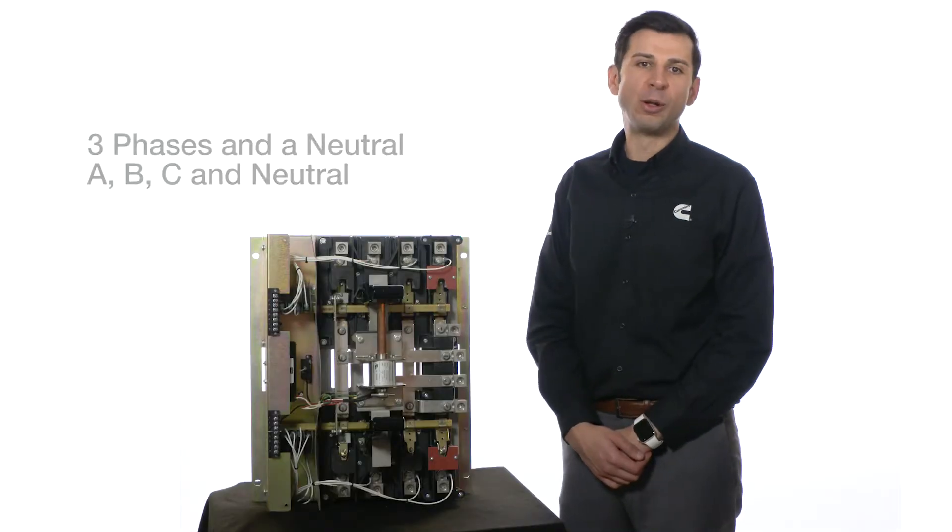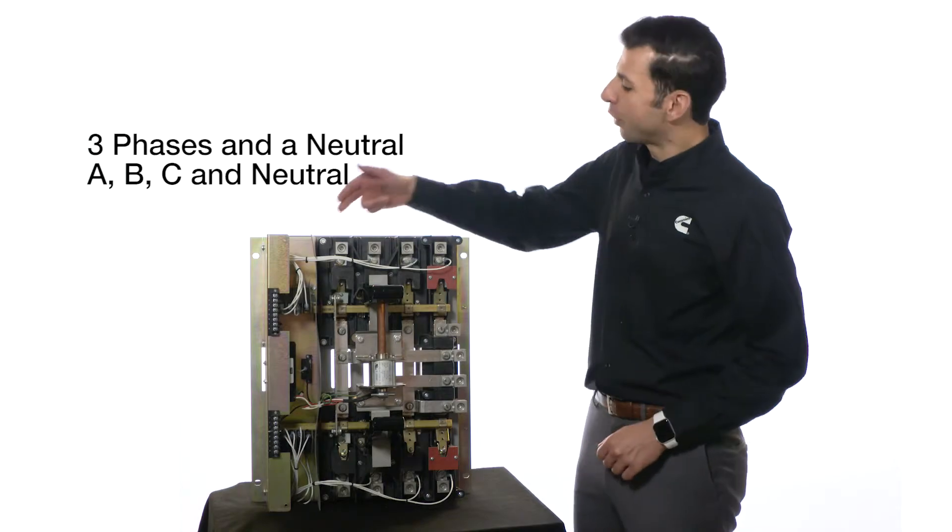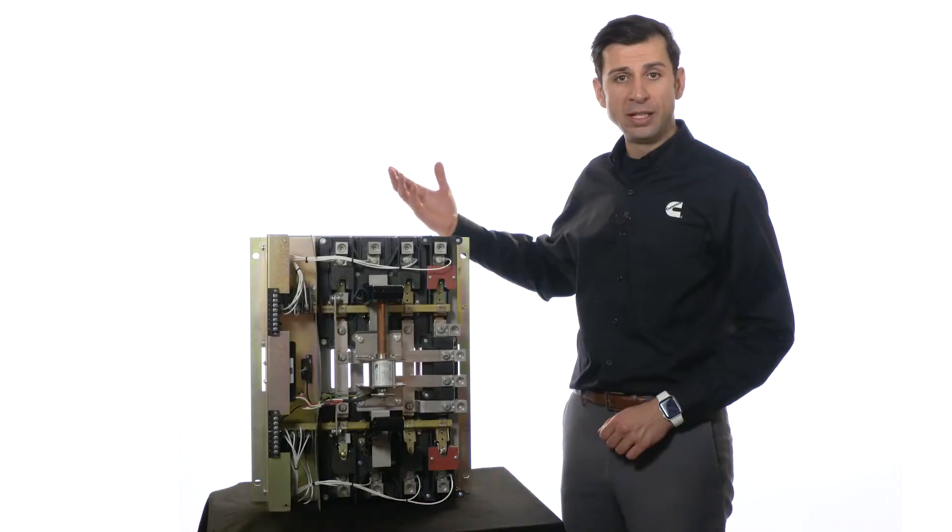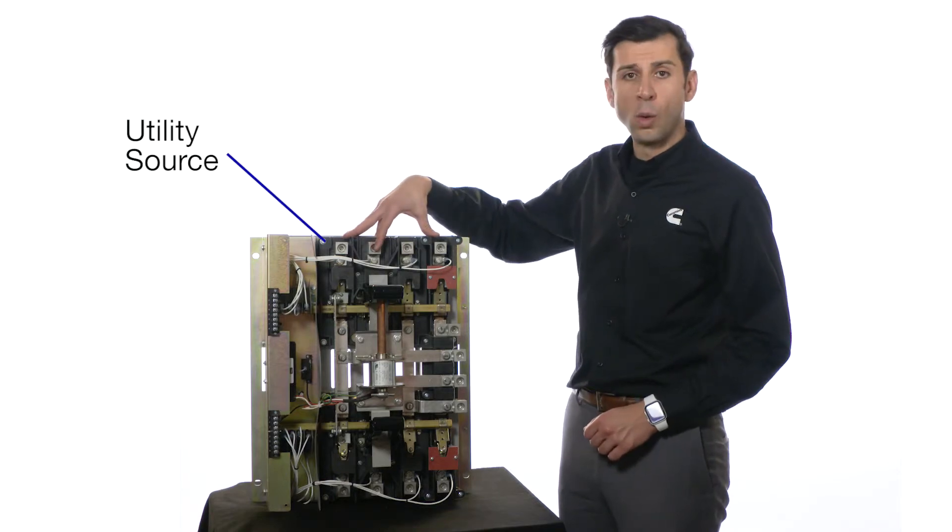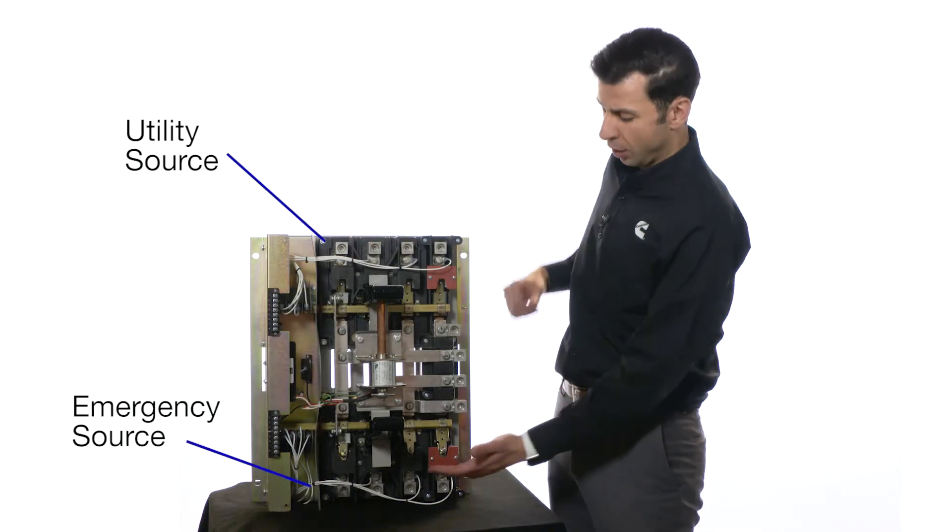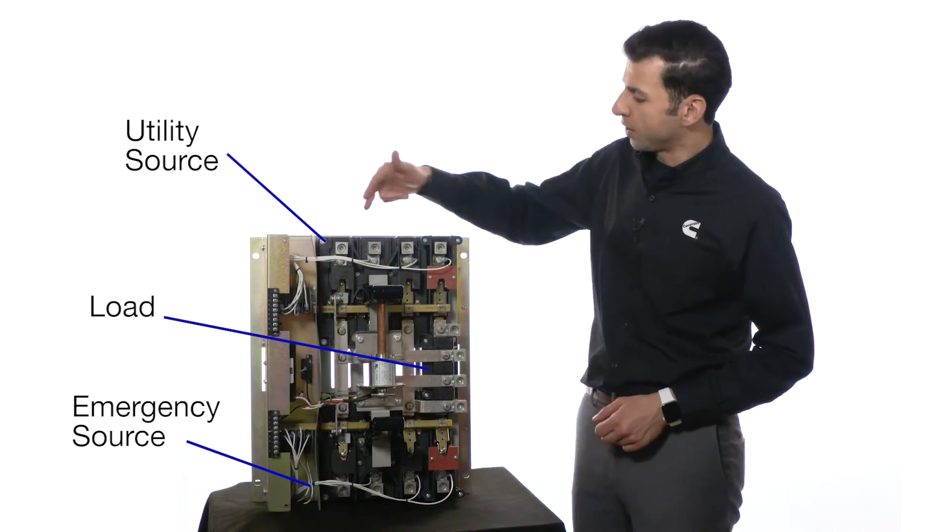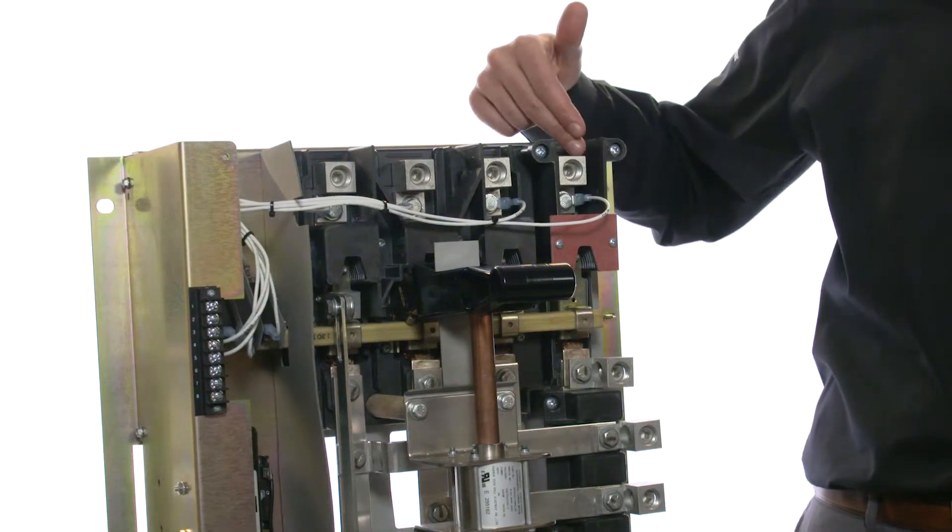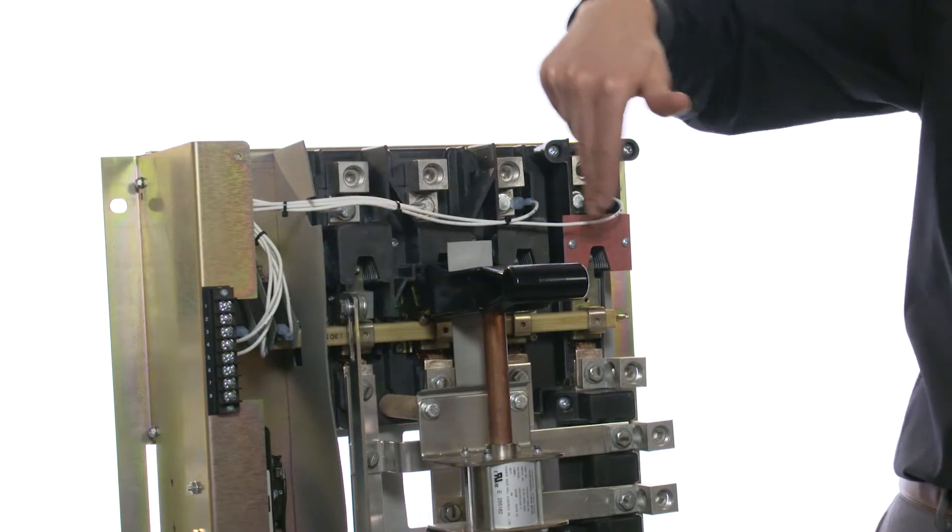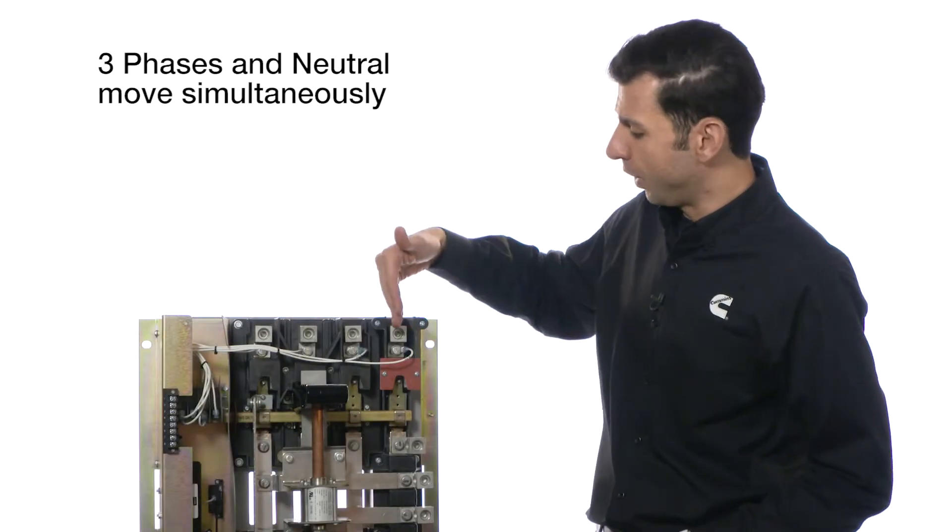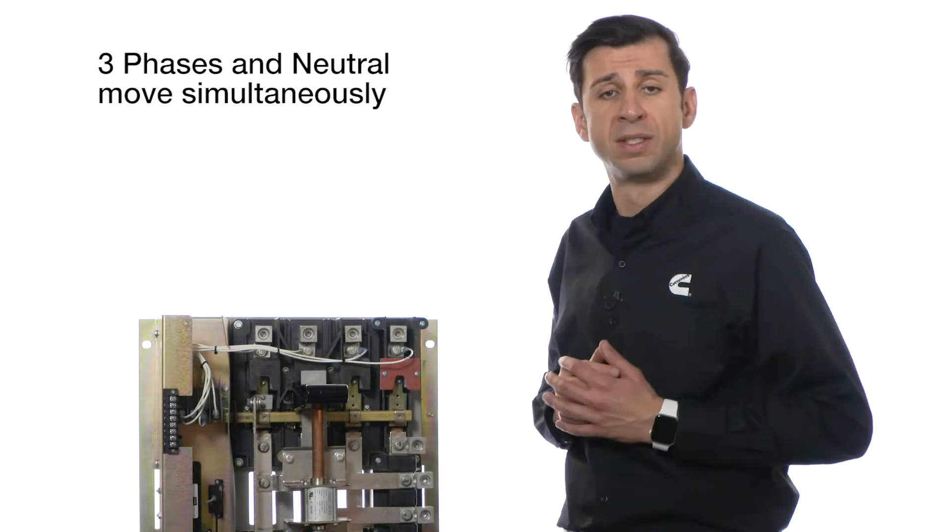This transfer switch is a four-pole, three-position transfer switch: three phases and a neutral, A, B, C, and neutral. The utility can be connected on this end, while the emergency source can be connected on this end, and the loads are fed from this end. Notice how the three phases and the neutral are connected to the same connecting rod, so when the transfer switch transfers, all three phases and the neutral are moved simultaneously.